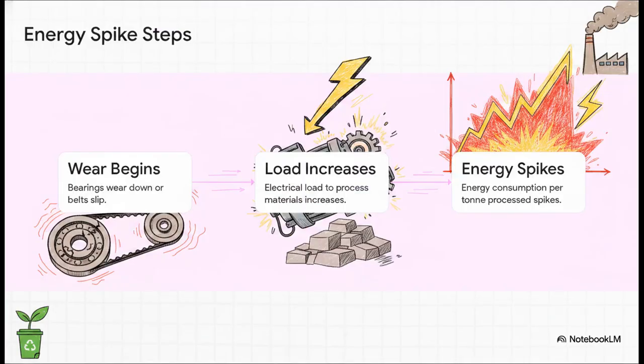Then there's the energy side of things. It usually happens like this. First, a bearing starts to wear out or a belt slips. Because of that friction, the machine has to fight much harder, so the electrical load required to process the material jumps up. Suddenly, your energy consumption per ton spikes. But here's the cool part. If you track that energy data alongside your maintenance logs, your basic energy dashboard suddenly transforms into an early warning system. You can spot mechanical degradation weeks before a part actually snaps.